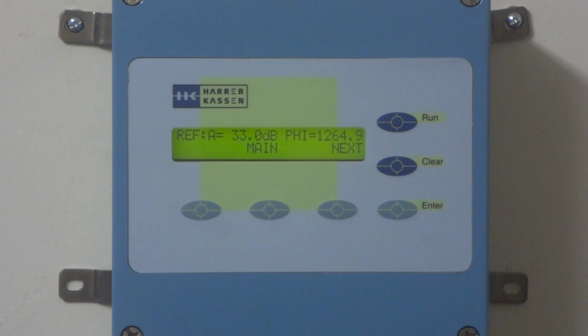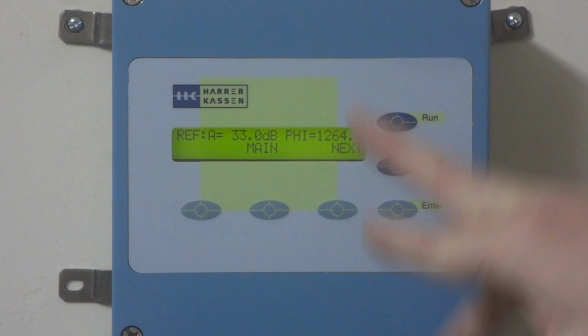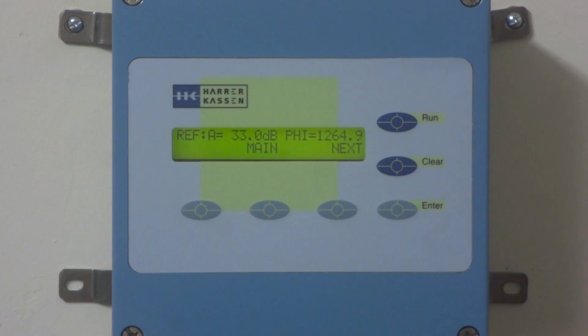Stability means that the attenuation doesn't change by more than a half, 0.5, and the phase shift doesn't change by more than 10. If either one of those things are happening, the process material is not stable enough to do a reference measurement.